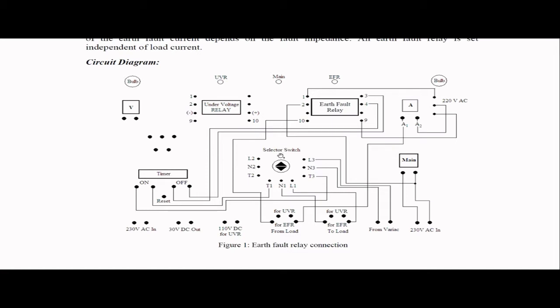So this increased current can be supplied by the transformer, and this is called the artificial fault. Using this procedure, we can increase the amount of current, and this current will pass through the relay coil. The relay senses it as a fault and the relay works accordingly. So this is our main purpose.